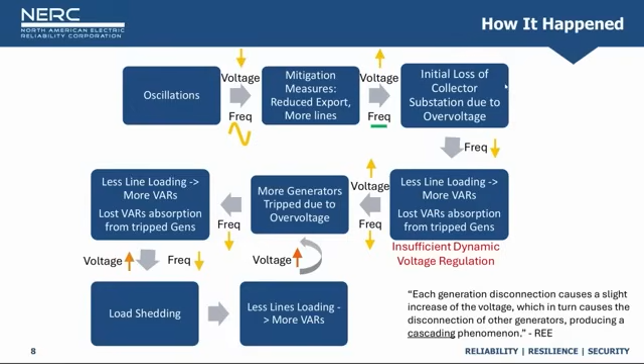They switched off some shunt reactors. They reduced their export to France. These actions also caused voltage to increase. Further generators that were to absorb reactive power did not do so. I'm not sure why. Something more to learn there. After the loss of the first collector substation due to overvoltage, voltage increased more due to less power flow. As you can imagine, less power flow, less lightly loaded lines, voltage goes up, Ferranti effect. And due to the less power flow on those lines, it caused more reactive power and, of course, the loss of reactive power absorption by the tripped units that were coming offline.